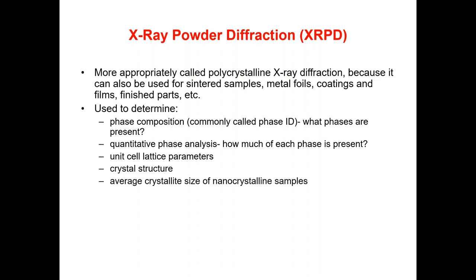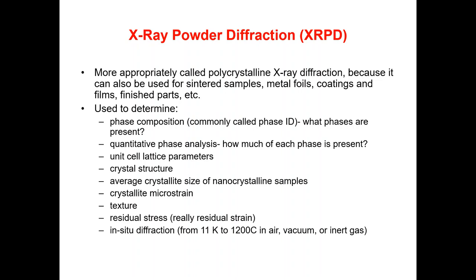XRPD is used to determine phase compositions — commonly called phase ID — that is, what phases are present in the sample. It can also be used for quantitative phase analysis, to find out how much of each phase is present, as well as unit cell lattice parameters, crystal structures, average crystallite size of nanocrystalline samples, micro-strains, texture, residual stress, and in-situ diffraction from 11 Kelvin to 1200°C in air, vacuum, or inert gas.